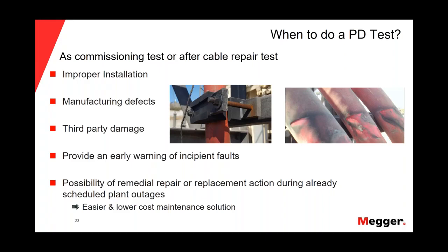For instance, if the cable was bent too much, we will have a chance to find that kind of issue with partial discharge. As you can see in these pictures, the person that fixed the cable in the holder exceeded the torque, and for this reason, they deformed the insulation of the cable. So for that kind of problem, partial discharge will help us.